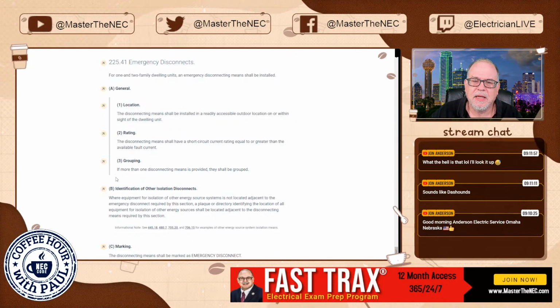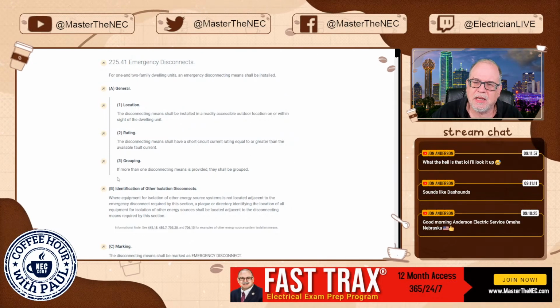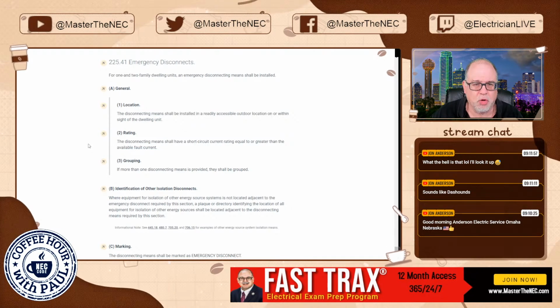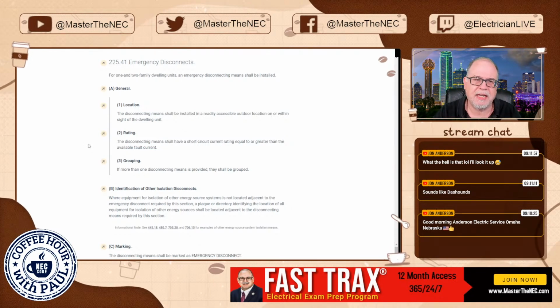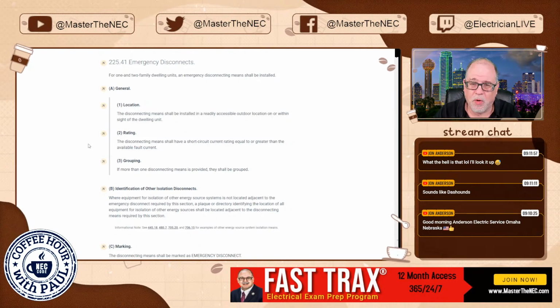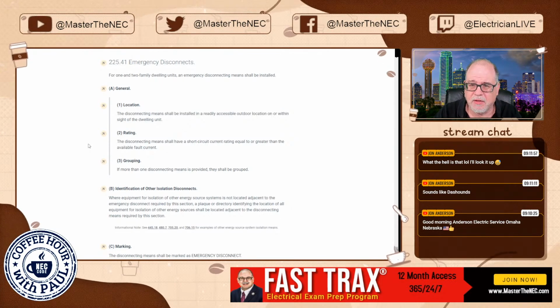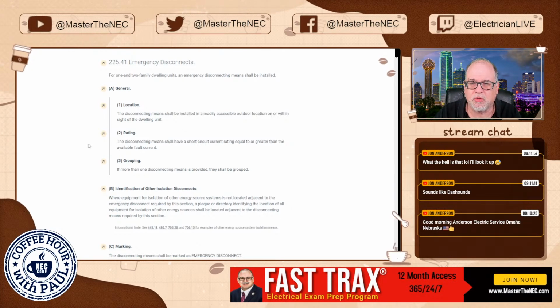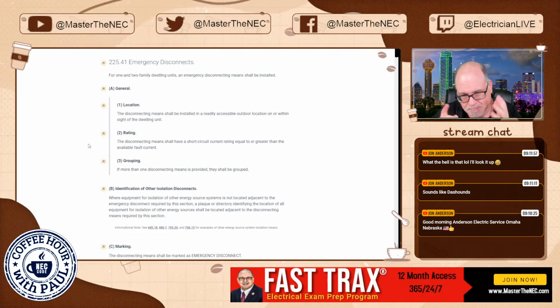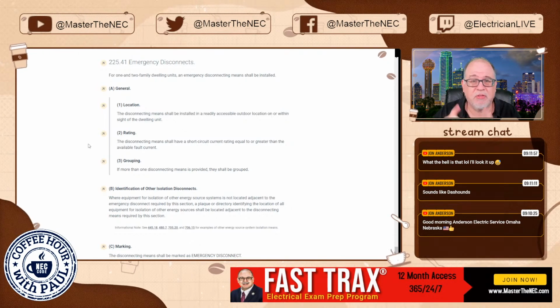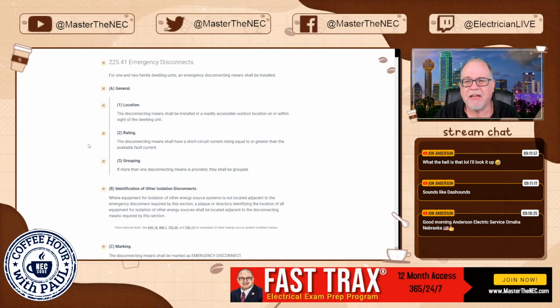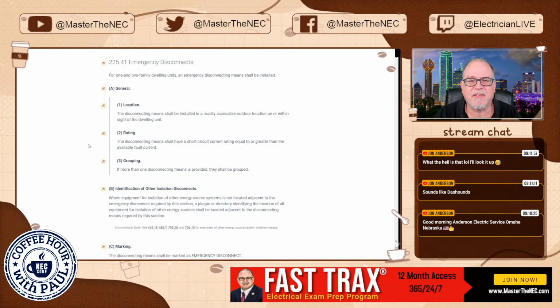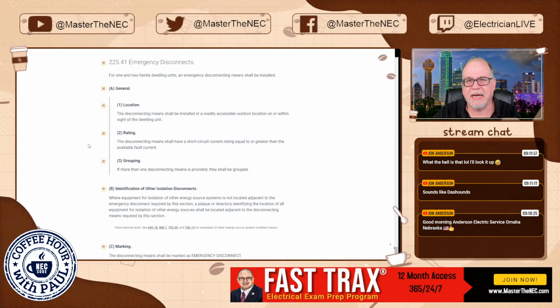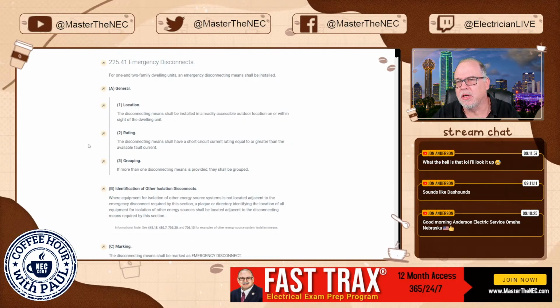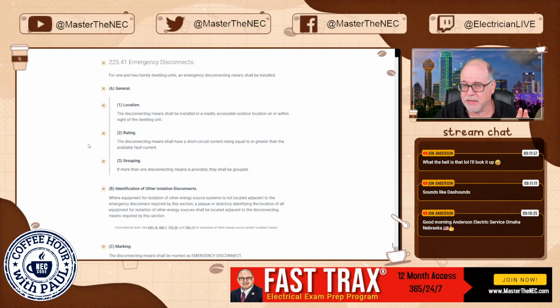In grouping, if you have more than one disconnecting means provided, then they shall be grouped. So the emergency disconnect, if you happen to have more than one, they got to be grouped. The short circuit current rating has to be equal to or greater than the available fault current. Okay. And this emergency disconnecting means has to be located on or within sight of the dwelling unit outside. Very similar to what it was for services, okay?